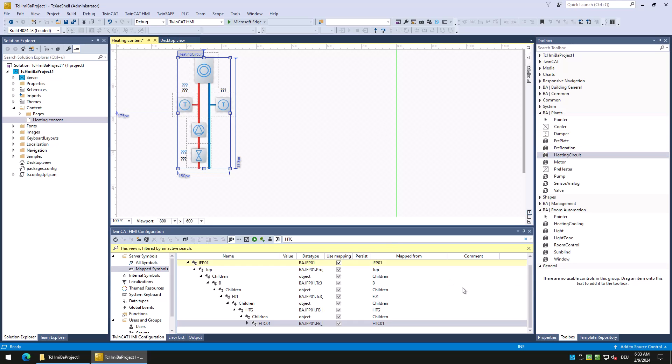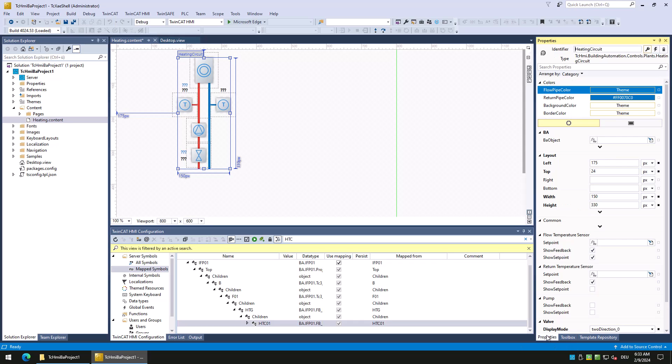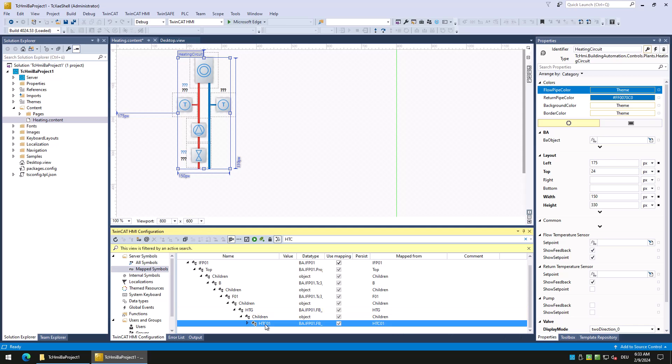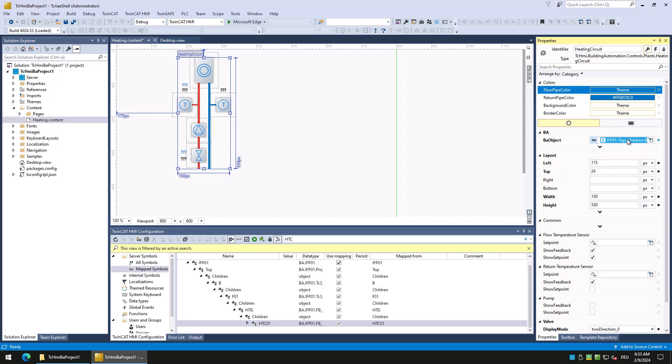Then we select the heating circuit and create a data binding to the BA object attribute. To do so, we can simply drag and drop the heating circuit instance from the TwinCAT HMI configuration window onto the BA object attribute. That is all we need to configure for the heating circuit itself.